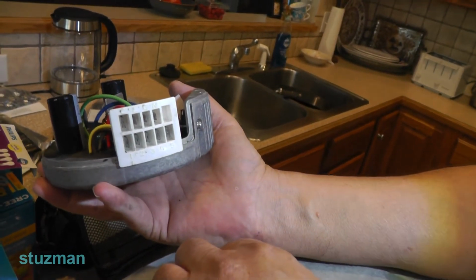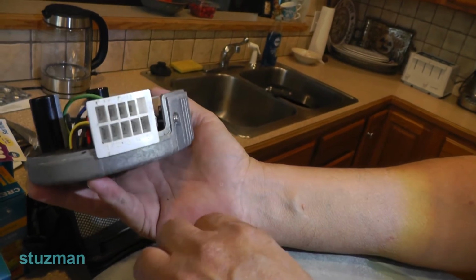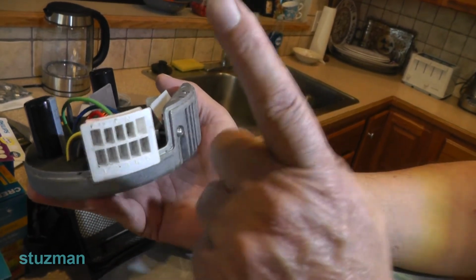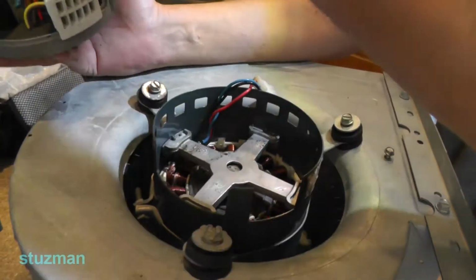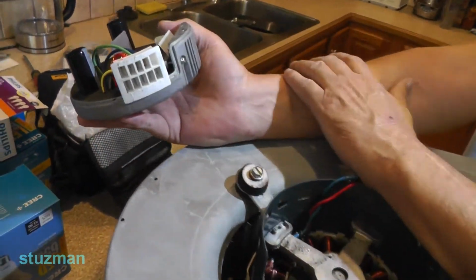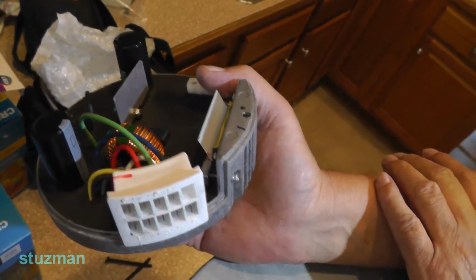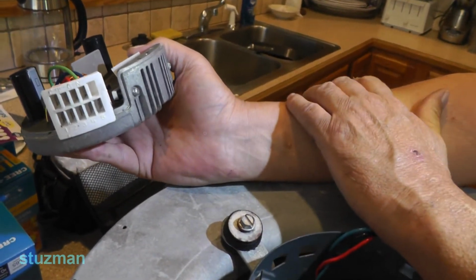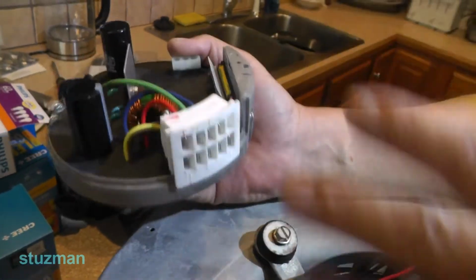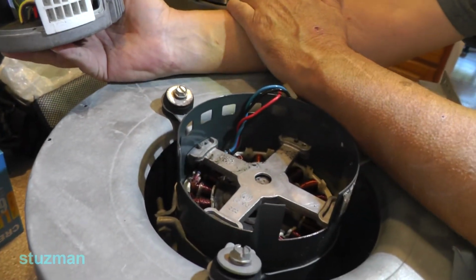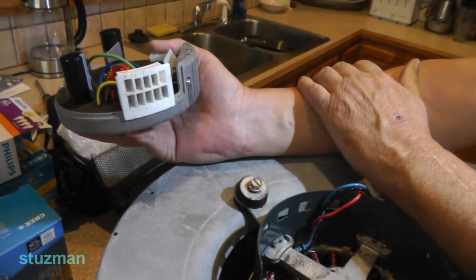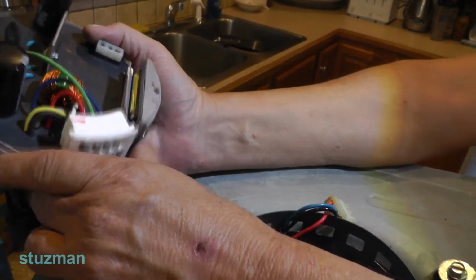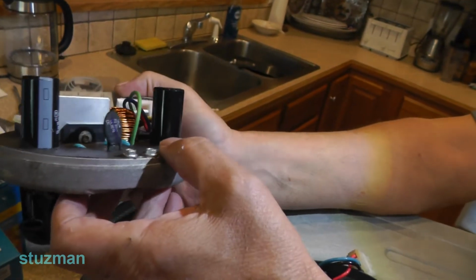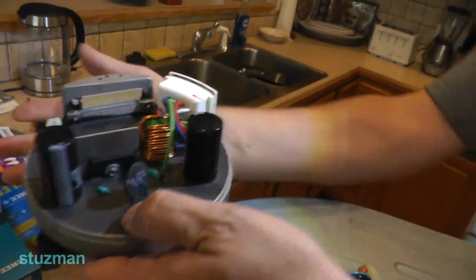And most of the time, they're not going to separate this unit out and say, okay, your motor is bad. They're going to replace the whole entire thing. Now, depending on how the tech feels that day, your price for this is going to vary from $1,200 to $2,000. So for this one piece? Well, they're going to replace the whole entire unit. Oh, gotcha. So you're looking at $1,200 to $2,000. And I did not want to go that route, at least not to start with. So what we're going to do is see if we can do something here. But anyway, let's do some more checks.